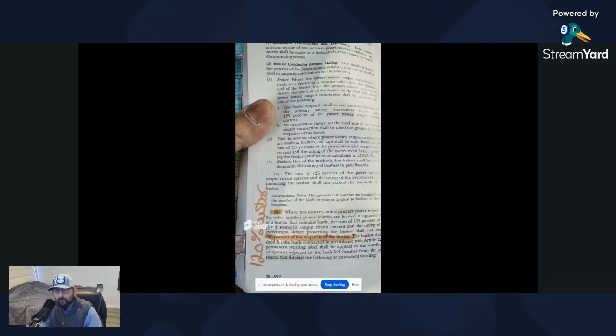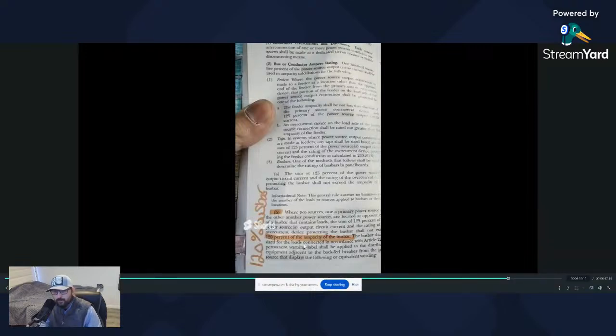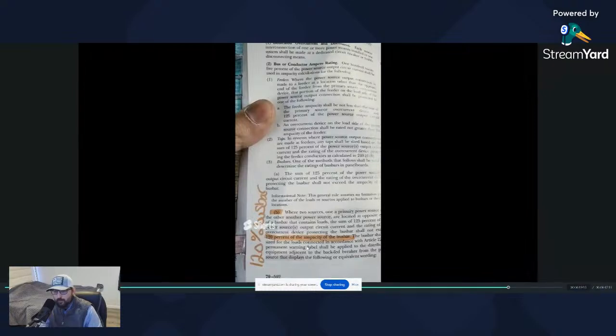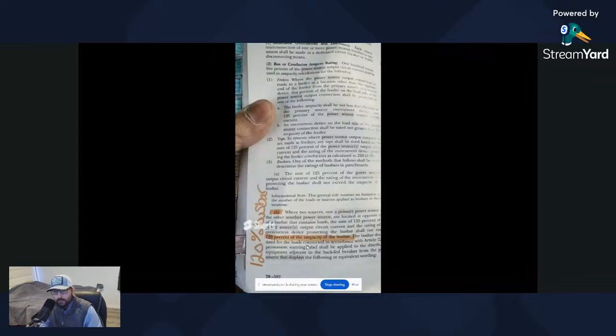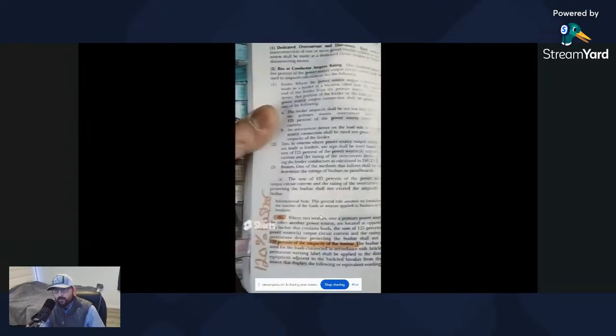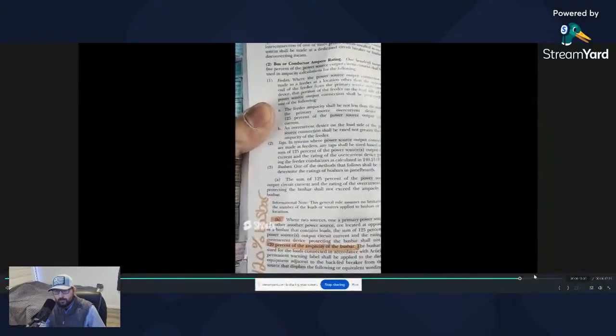Next, you got to be 120% of the ampacity. Ampacity just means the amperage capacity. So if we want 120% of the ampacity of the bus bar, we would multiply 1.20 times 200, which is what the bus bar is rated for, and that would give us 240. And next, you're going to subtract the main of the panel. So if we have 240, we subtract 200 amps, that gives us 40 amps. So the maximum breaker that we can put on this solar would be 40 amps typically. Come on, moving on.